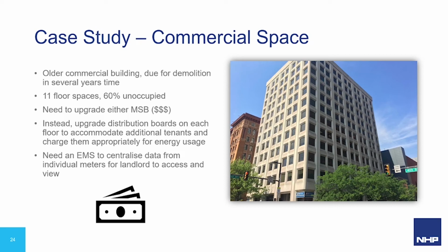The owner and landlord of the building wanted to increase their offer of tenancy space prior to the planned demolition of the building in several years' time. The current configuration of the main switchboard did not meet requirements for billing multiple tenants separately, and it didn't have room to accommodate the additional meters required.